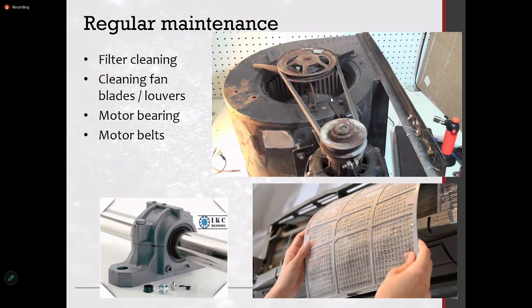And when it gets clogged, then the blowing does not happen to the optimum level. And actually the pressure inside the space also increases trying to blow air. So in AHUs, you monitor the duct pressure, we call it, or the differential pressure. So the pressure difference before the filter and after the filter to actually see whether the filters are clogged. So regular maintenance of the filters is important so that you get a proper blowing.